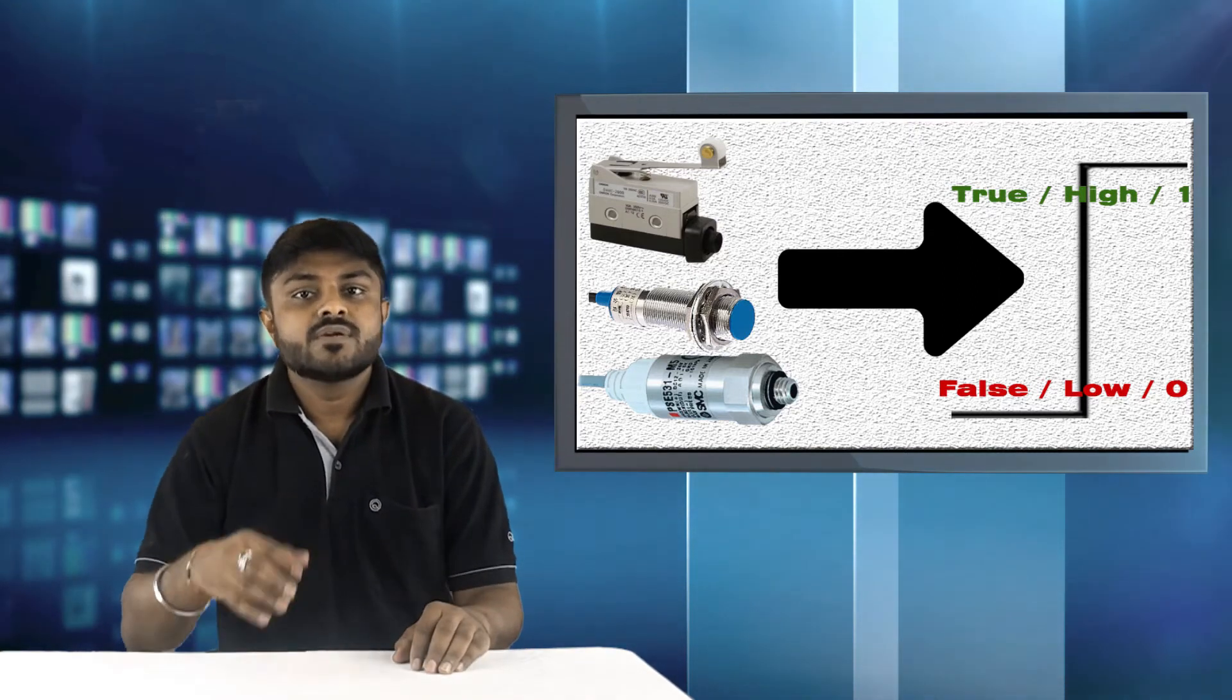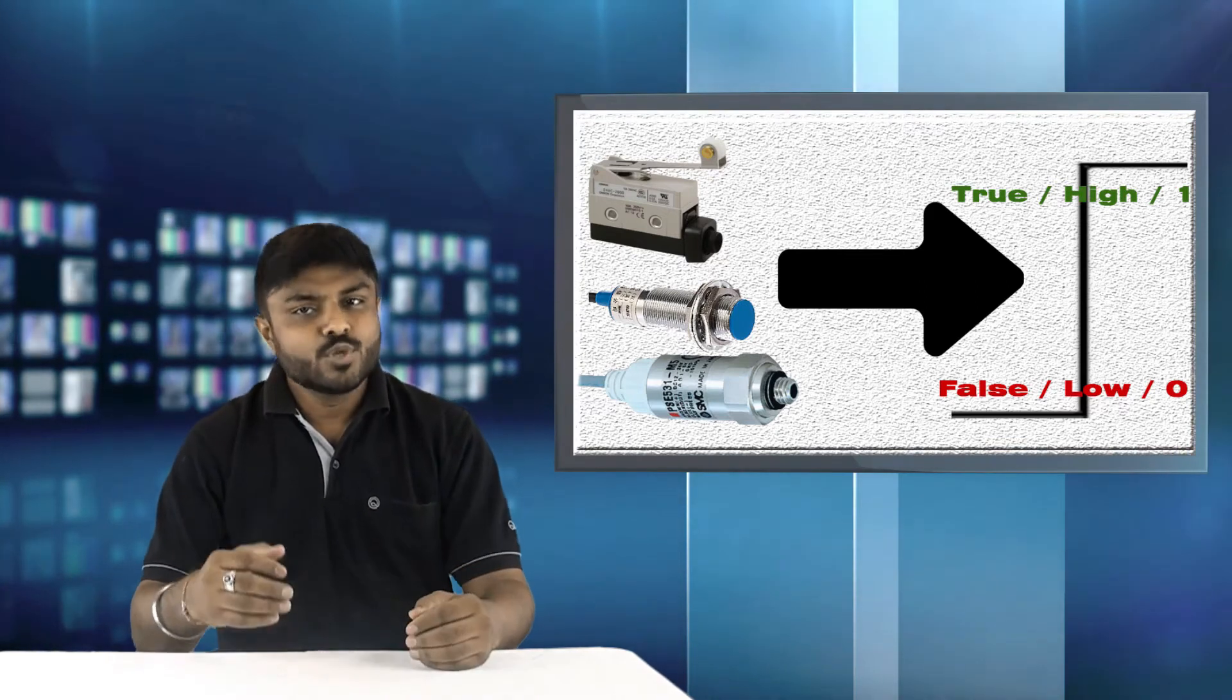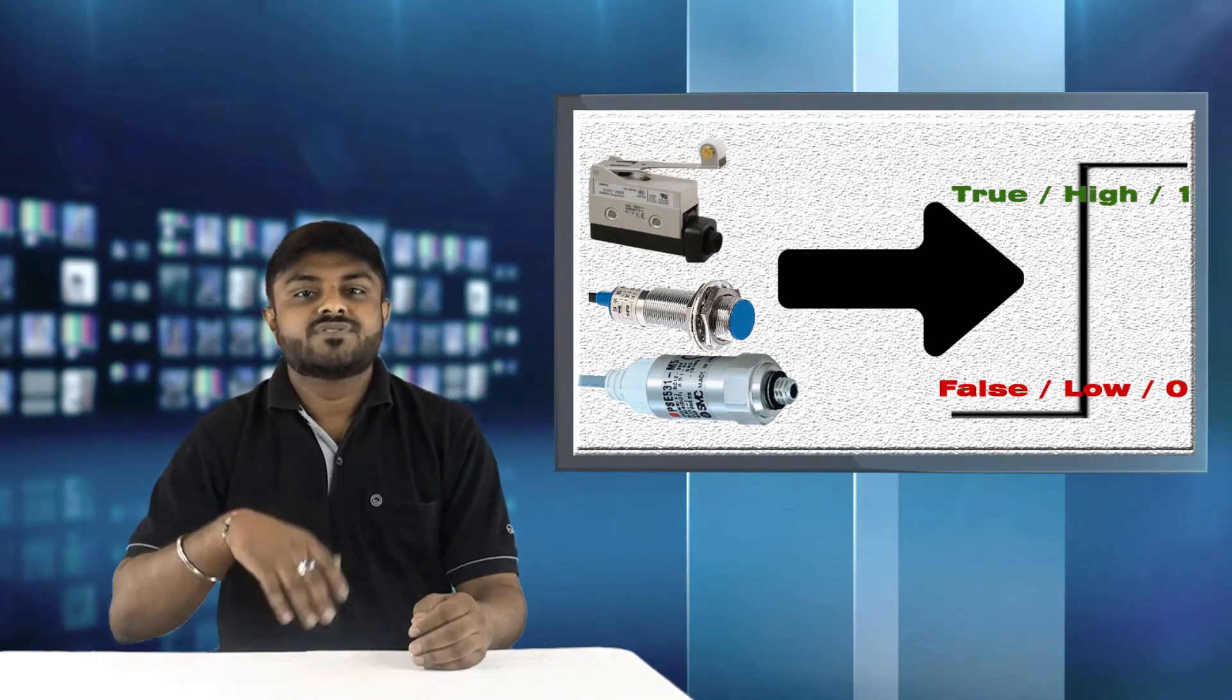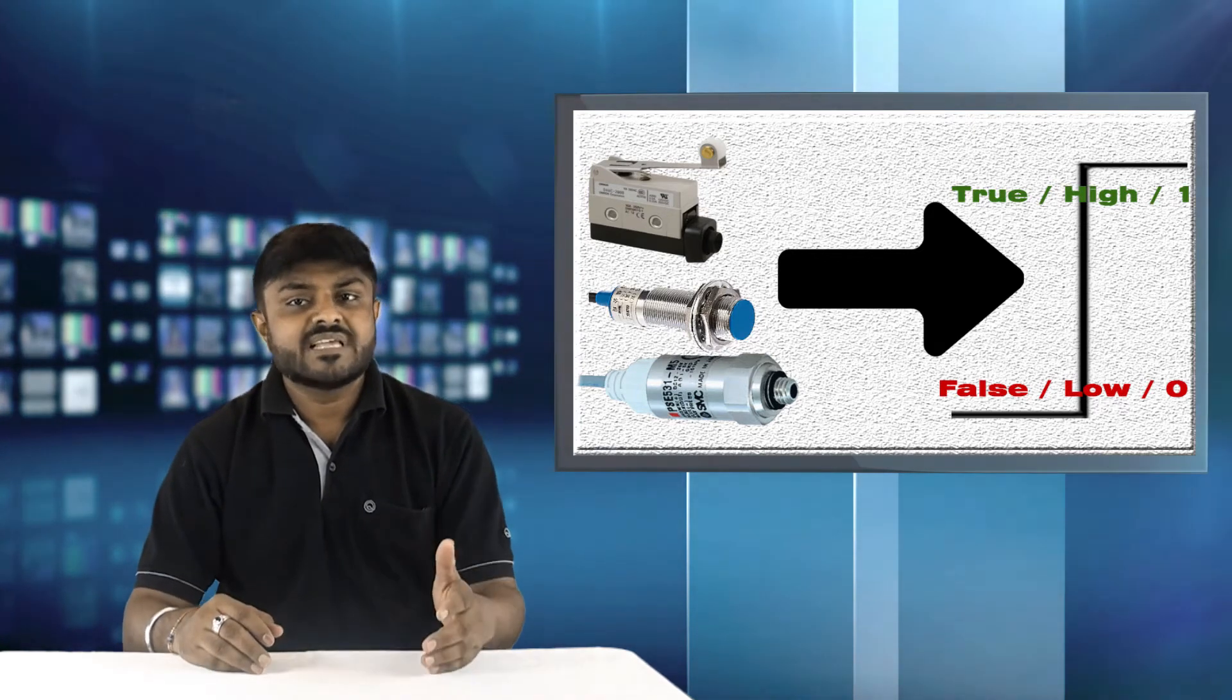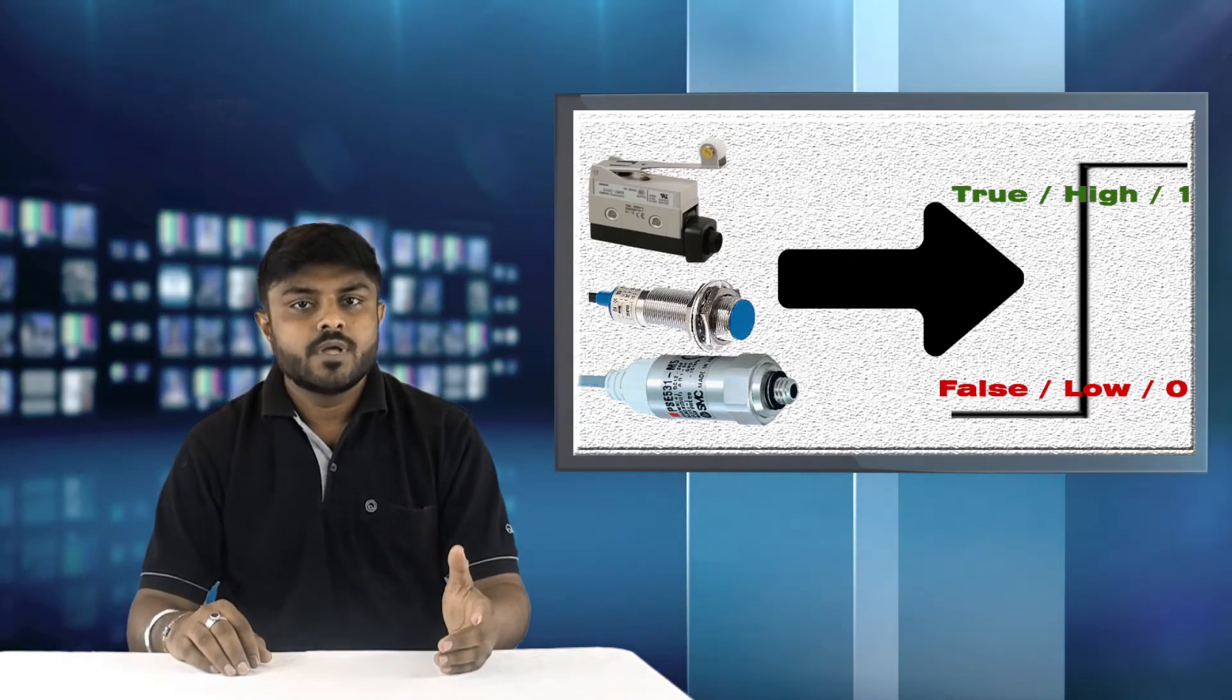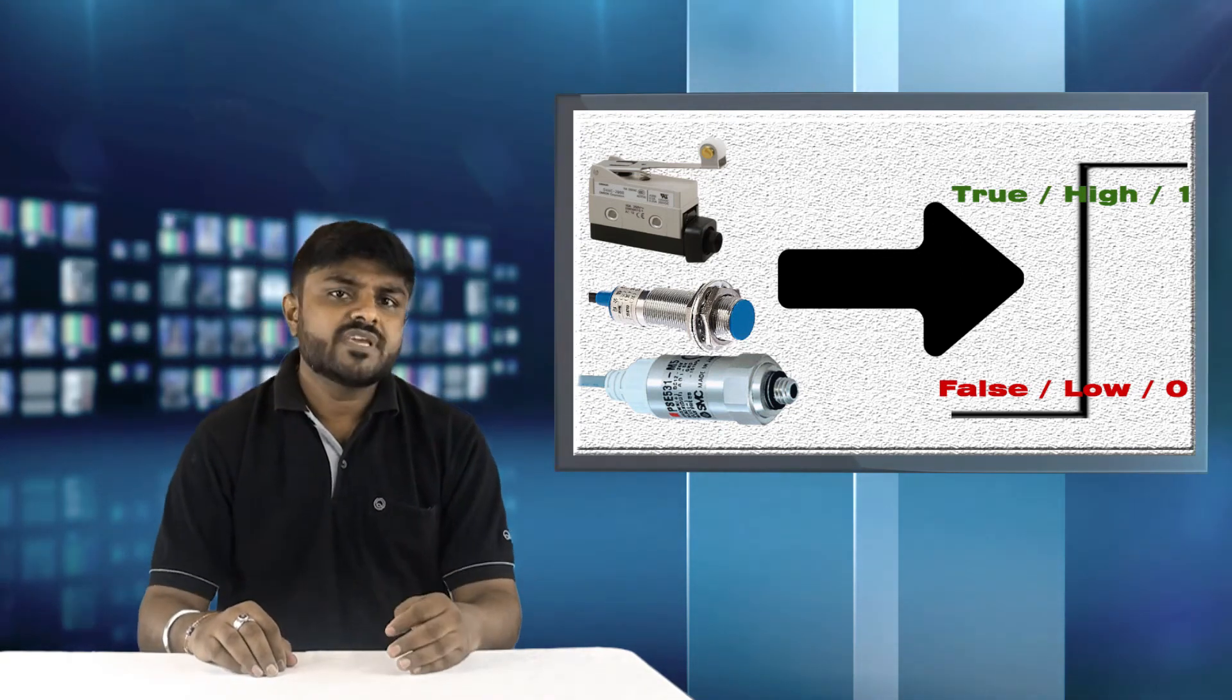It means the sensor output is high, true or we can say 1. While sensor is not sensed, 0V DC is observed between normally open contact of the sensor with respect to ground. It means the sensor output is low, false or we can say 0.